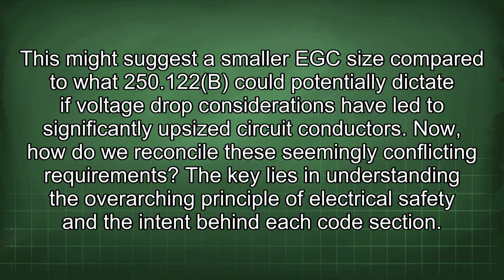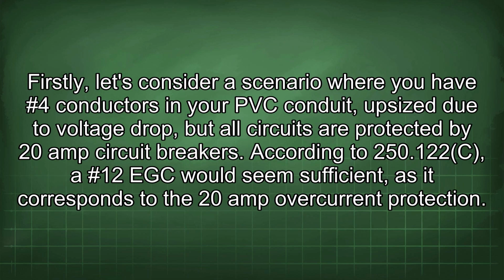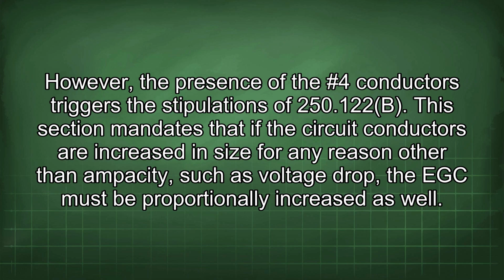Now, how do we reconcile these seemingly conflicting requirements? The key lies in understanding the overarching principle of electrical safety and the intent behind each code section. Firstly, let's consider a scenario where you have #4 conductors in your PVC conduit, upsized due to voltage drop, but all circuits are protected by 20 amp circuit breakers. According to 250.122(C), a #12 EGC would seem sufficient, as it corresponds to the 20 amp overcurrent protection. However, the presence of the #4 conductors triggers the stipulations of 250.122(B). This section mandates that if the circuit conductors are increased in size for any reason other than ampacity, such as voltage drop, the EGC must be proportionally increased as well.